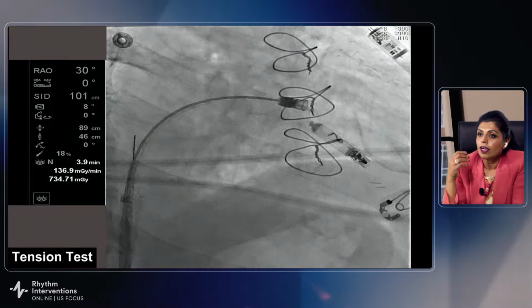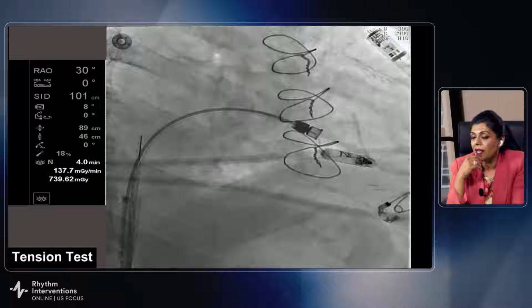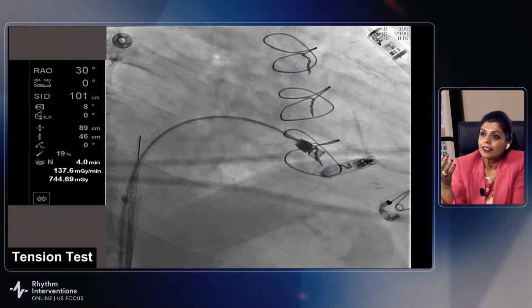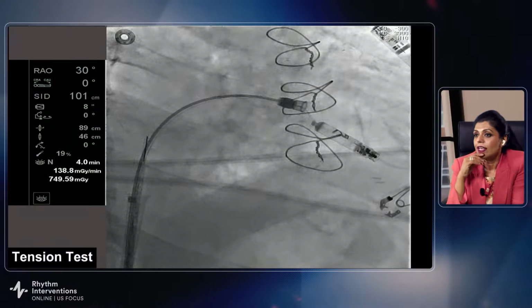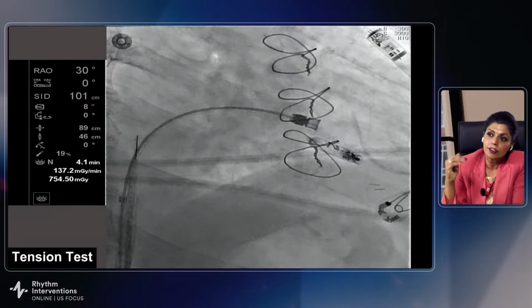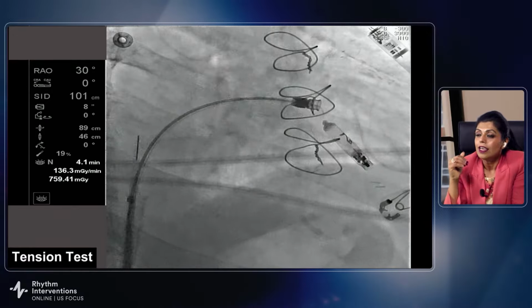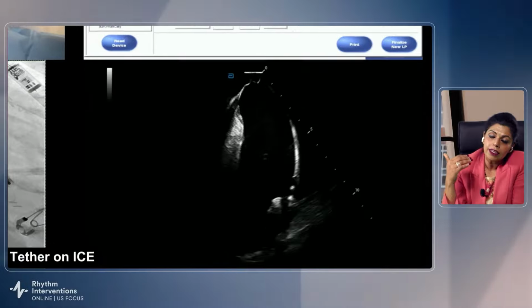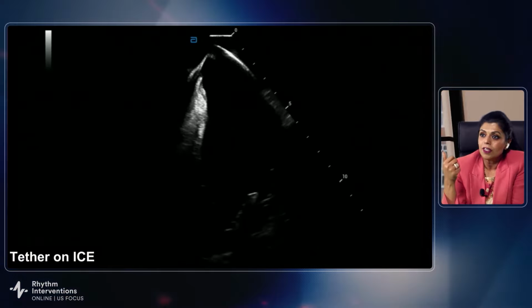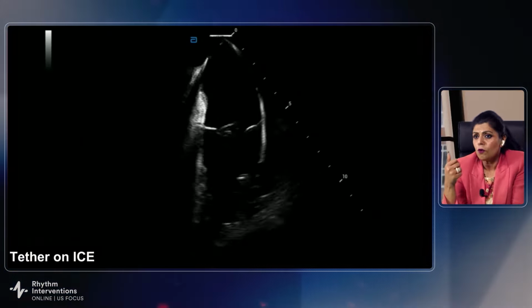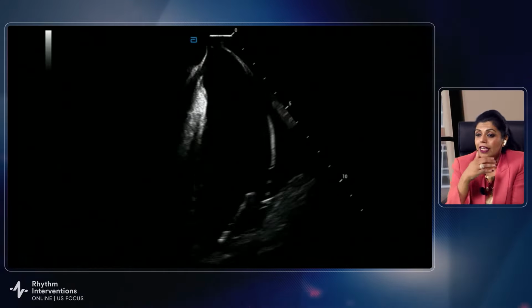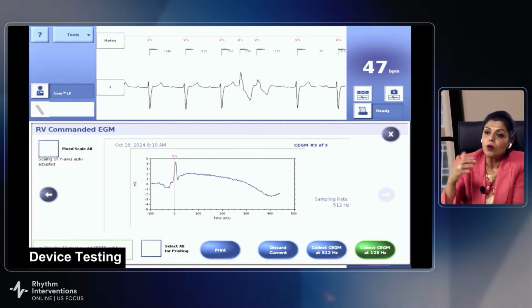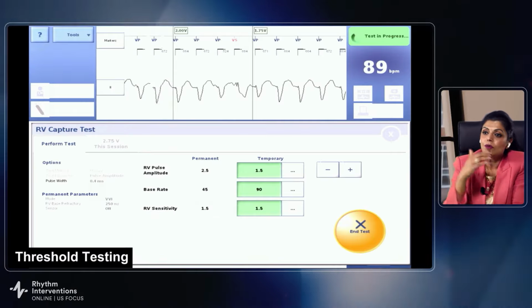And once you deploy or implant that helix, you take the device in, you undock the device, and you do this deflection test to look at the stability. The things that I look at for stability are, one, electrical stability. So we're looking at the electrical numbers, looking for that injury current to go up. We're looking for that impedance to rise with every turn.